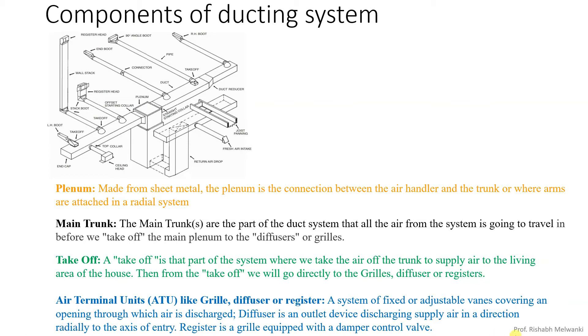A diffuser is an outlet device discharging supply air in a direction radially to the axis of entry. There are different types of diffusers. A register is a grill equipped with a damper for airflow control. In a register you can change the direction of air, whereas in a grill you will have a fixed type of vane. So we have grill, then diffuser, and then register.